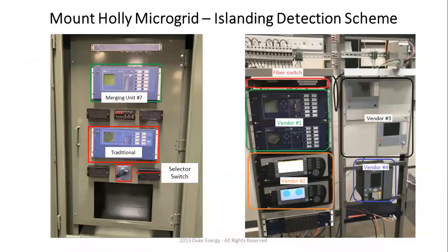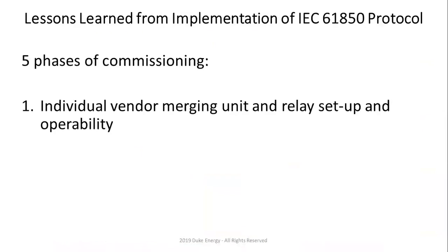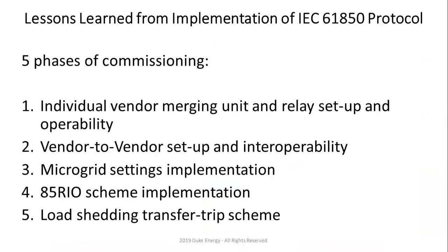On the right side, what we decided to do is put merging units from 4 different vendors, and on the back side, we have relays from 4 different vendors. If you take a look at everything with IEC 61850 based on the standard, you can mix and match, right? So the idea was to do 5 phases of commissioning. Number 1, we get one vendor just to read their own units, so each of these 4 vendors should be able to read their own units. Then next, each vendor should be able to read other vendors' merging units. Then we would implement settings, and then we would do the 85 RIO scheme to enable seamless islanding, and also a load shedding transfer trip scheme would be number 5, right? So we managed to get to number 3 now.